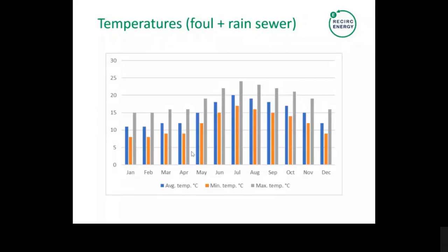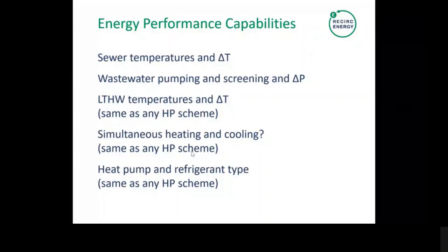In terms of energy performance, it's all related to the heat pumps - the sewer temperatures we're feeding them, the delta T, and as with any heat pump, the low temperature hot water temperatures and delta Ts, whether simultaneous heating and cooling can be done using the same heat pump, and the heat pump refrigerant type, which can affect efficiency. Wastewater pumping and screening also matter - if there's a lot of pumping over a long distance with high static lift, that all has to be taken into consideration for the parasitic electrical load.